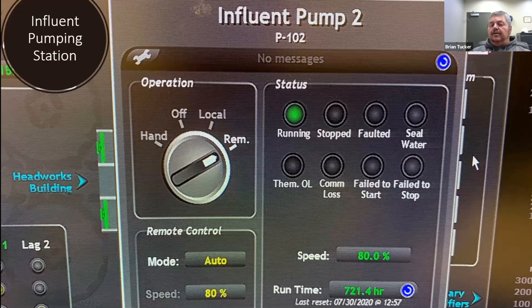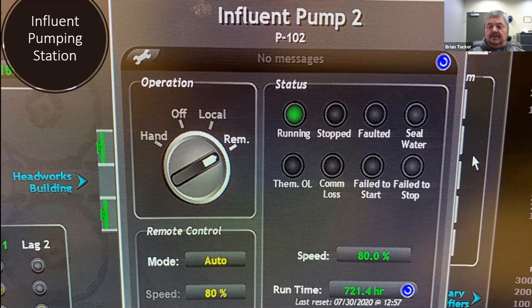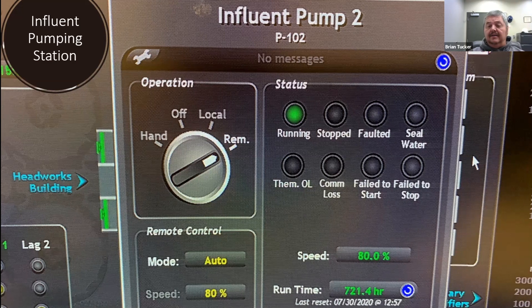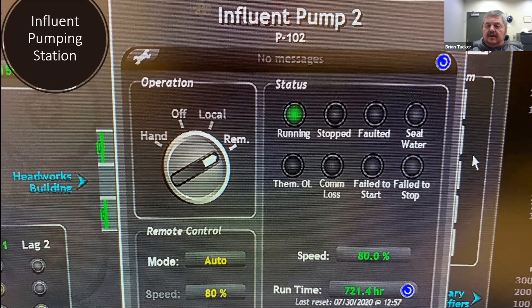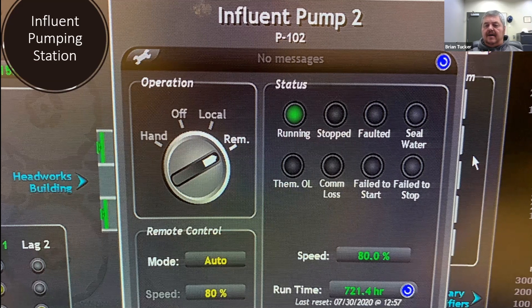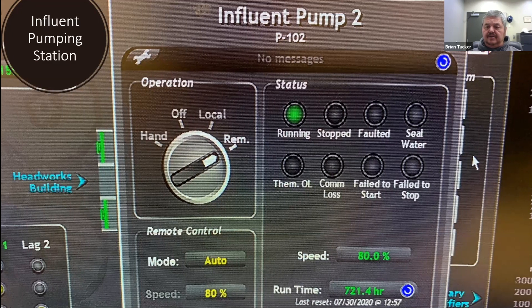Our influent pumps are vertical turbine pumps, 23 feet below the deck. Monitoring their efficiency, you really better find out they need maintenance before you call a maintenance person over. What we do is trend our pump speed versus gallons per minute output. When we see that GPM output start to drop at a given percentage of speed, we know we're starting to lose pump efficiency, and it can trigger that next maintenance.